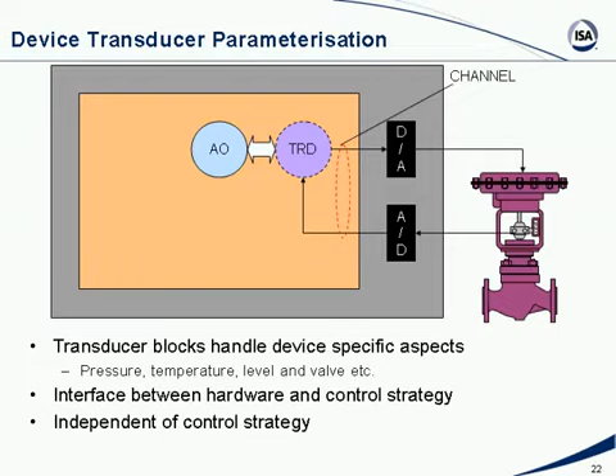Like we talked a little bit about in the question and answer session, okay? Foundation Fieldbus is really super for PID regulatory types of control, okay? But there's no variable speed drive using Foundation Fieldbus. So if you have variable speed drives in your plant, you have to connect them some other way, for example, using Profibus DP or DeviceNet. Same thing if you have lots of switches, proximity switches, lights, pilot lamps, etc. These don't talk Foundation Fieldbus either. So typically that would be done using DeviceNet or ASI bus.